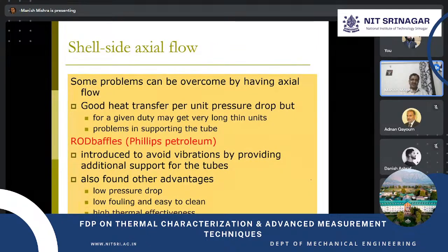There are issues with the shell side flow. What happens when fluid flow takes place only on the shell side? There are certain other problems. Vibrations are there, the supporting of the tubes may be an issue, deposits and air pockets may be a problem. All the things cannot be eliminated or checked up to 100%, but we need to see how periodically this can be taken care of. Naturally, each and every heat exchanger has a certain preventive maintenance schedule. If it is meeting that time schedule, say 6 months or 1 year or whatever, then it is fine. But if it is occurring frequently, it is leading to some other problem, and we should definitely take care of that particular problem.